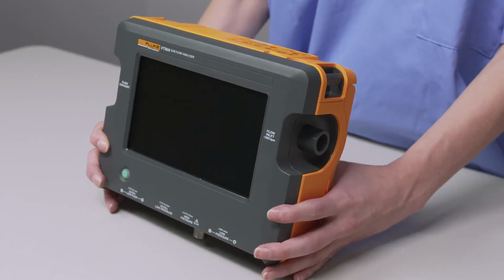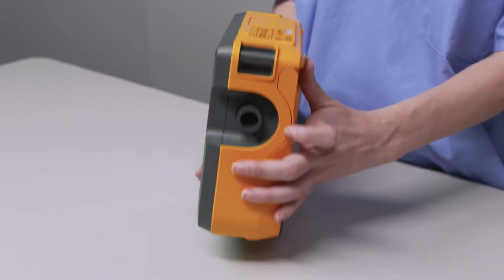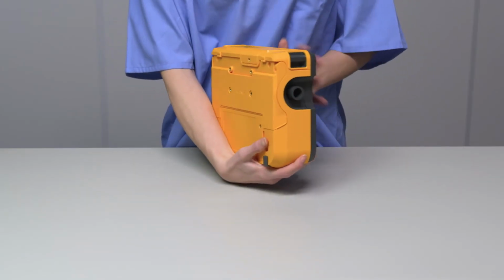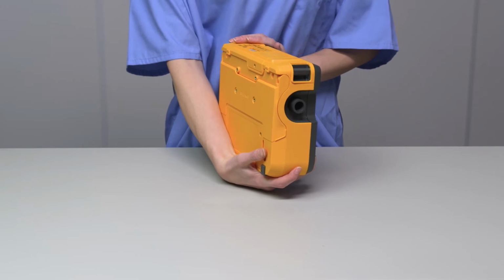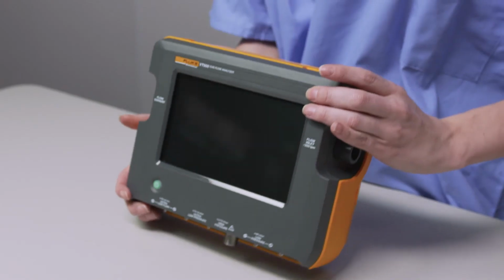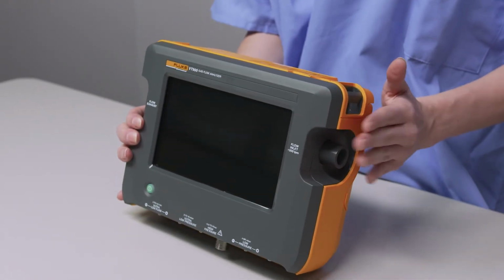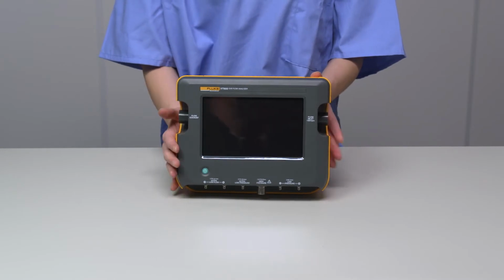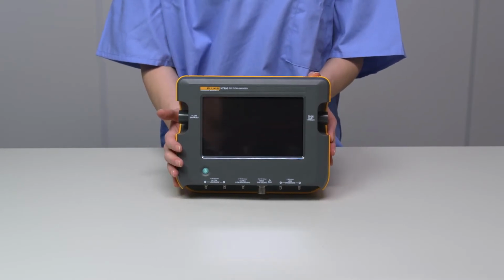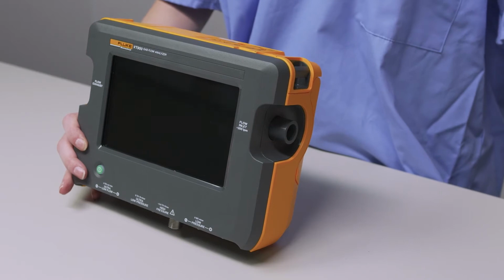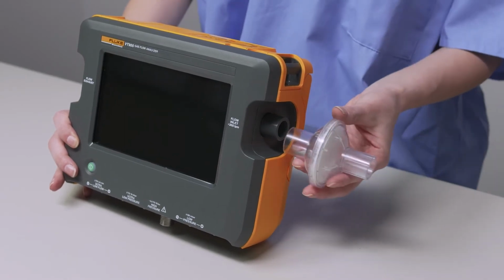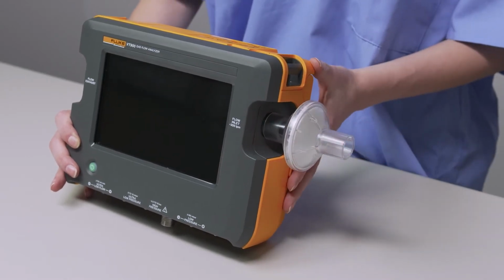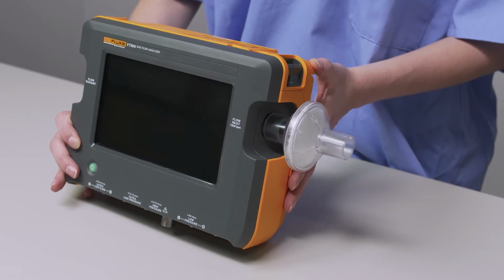On the right-hand side of the device, we have the flow inlet, and on the left-hand side, the flow exhaust. For bidirectional flow testing, we hook our respiratory tubes on the right and our test lung on the left. When using the airway channel, it's best to use the external filter. Snap the filter on the inlet to help keep measurements steady and protect the unit from contaminant matter.